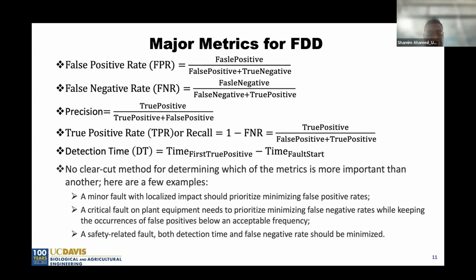At the same time, you should keep the occurrence of false positives below an acceptable frequency. If you have a complex fault related to safety issues, you definitely need to minimize detection time and false negatives, because with any safety-related fault, you need to identify it as soon as possible to avoid a major accident or big problem in the system. Detection time is one of the biggest things to consider: how fast can you detect that fault.